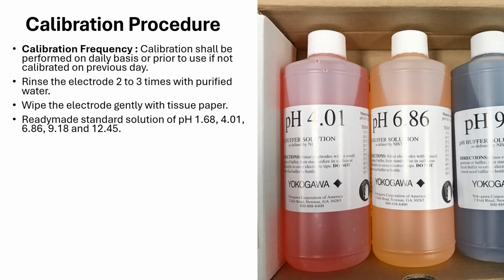For this pH meter calibration, commercially available ready-made standard buffer solutions can be used with pH values of 1.68, 4.01, 6.86, 9.18 and 12.45. A few are highly recommended, such as Merck and Sigma Aldrich make pH meter buffer solutions. These solutions help us to calibrate the pH meter across a range of pH values. Next, check the temperature of the buffer solution. The temperature affects the pH reading, so it's very important to verify this to ensure accurate calibration, right?